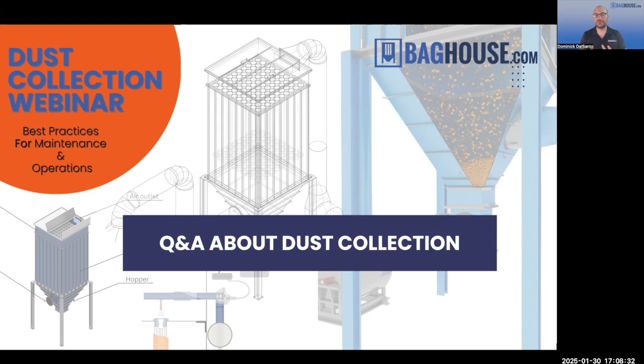This is a sign that it's undersized because those velocities inside are too high for the dust to fall off while the fan's running. So this is why we caution people when they're told that they're supposed to clean down at the end of the day. In most cases, with pulse jet baghouses, that's like a shorthand of we undersized it. You need to do this to give it breathing room again. It's like giving it CPR. Because if you turn the fan off, clean everything off, and then turn it back on, it's like everything's brand new again. The problem is then when you're running, right, it builds up and it can't keep up with itself long term.